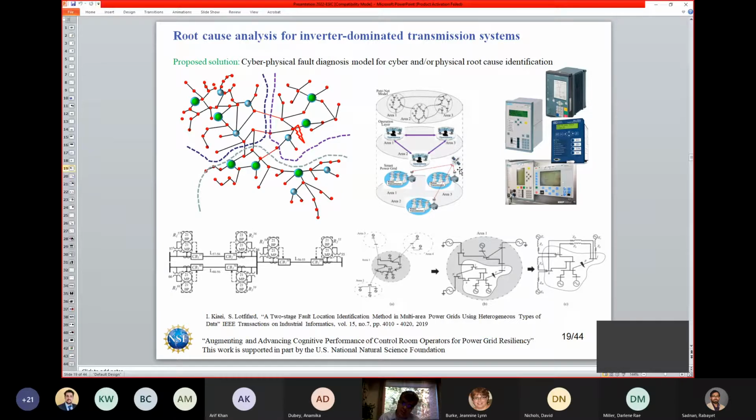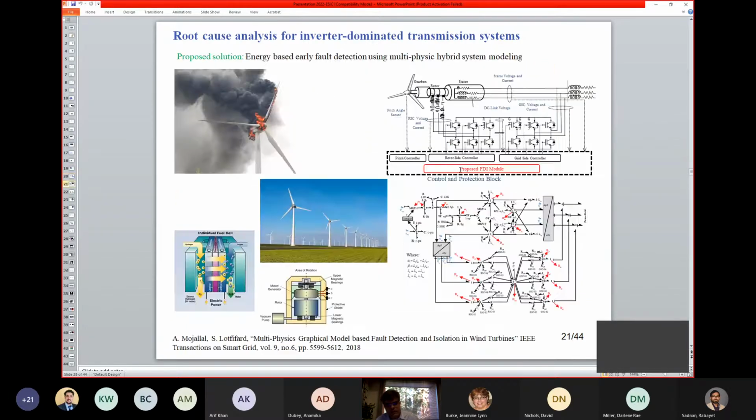It goes back to how the protective relay responds to these different fault characteristics. There are many relay functions that misoperate. Some of them are well known and well documented, and people are aware of them. Some of them we are trying to study in even more detail, looking at the measurement chain of the protection system, and then integrate that in the root cause analysis program that we have.